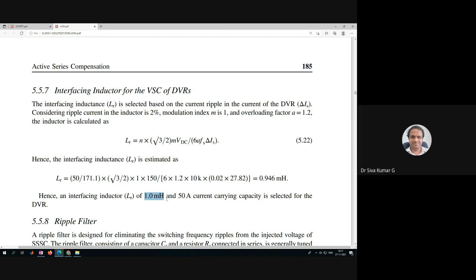There are different approaches in deriving the interfacing inductance, but it is not necessary to go through the entire derivation. Generally, the interfacing inductance for the VSC can be selected depending on the current carrying capacity of the particular phase. If it is 50 percentage of current, then you can consider it as 2 percentage; if a lesser current is there, then the percentage ripple current will be much higher. This particular design value we got is around 0.946 millihenry, about 1 millihenry. We can go for 2 millihenries also.